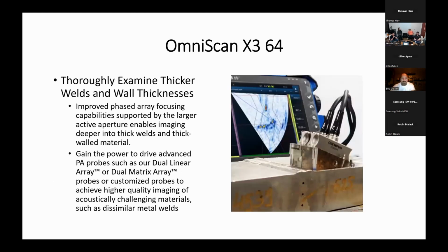So the 64's got improved phased array focusing capabilities that are going to help support larger active aperture elements. That's going to enable imaging deeper into thick wall material, hard to penetrate metal. We also gain the power to drive advanced PA probes such as DLA and DMA probes, or even customized probes, so we can achieve higher quality imaging of acoustically challenging materials such as dissimilar weld materials, or maybe something like stainless steel.